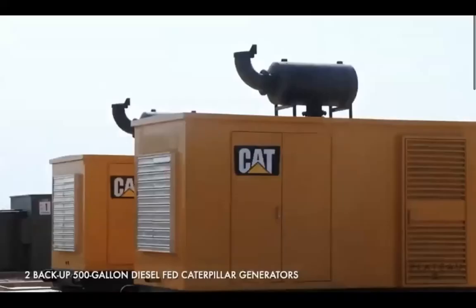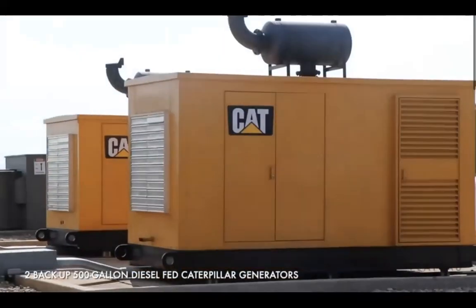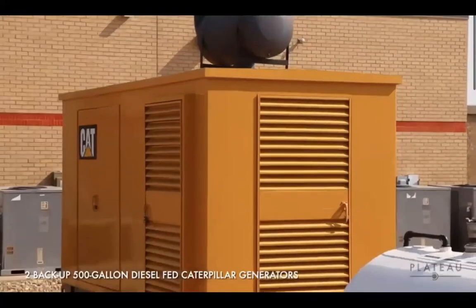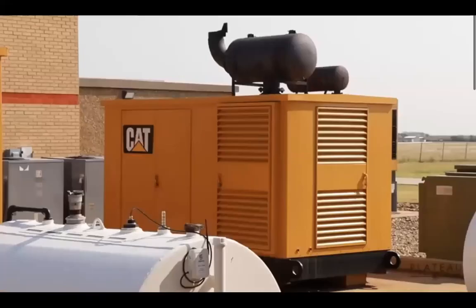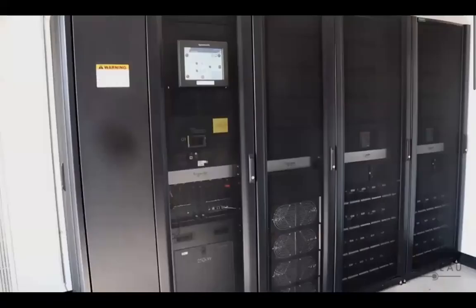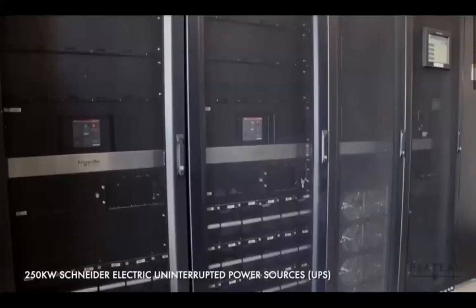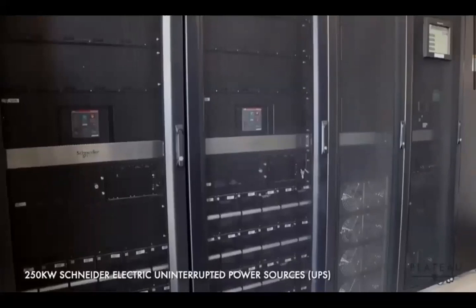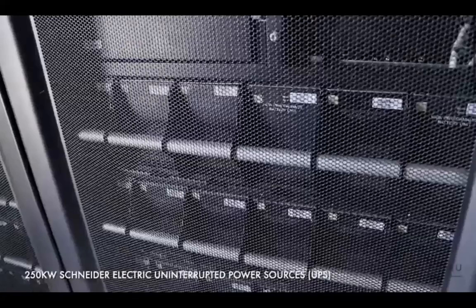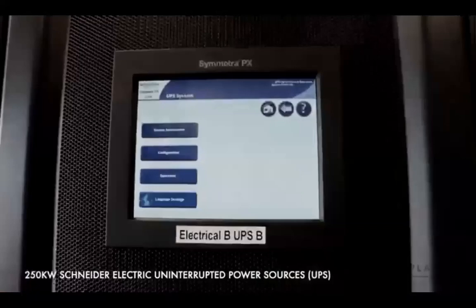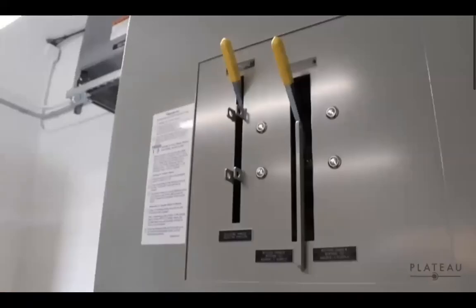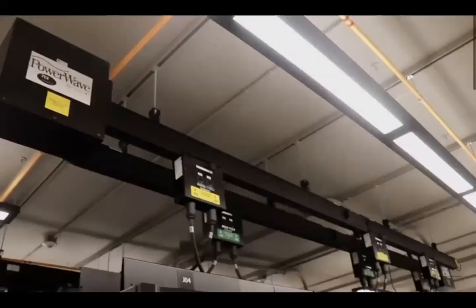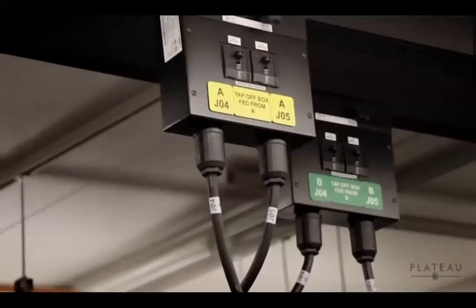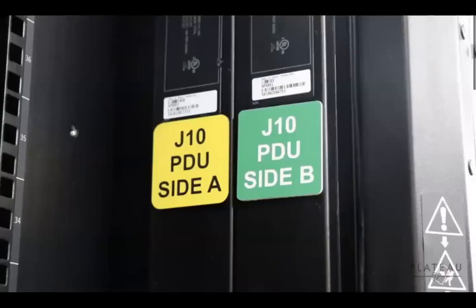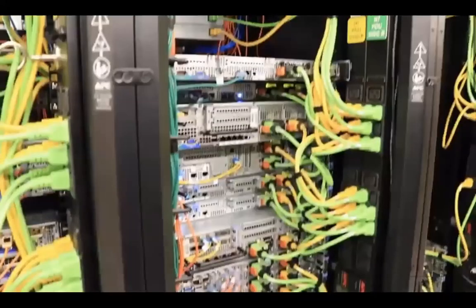Plateau ensures that the data center never sees a loss of power by having not one, but two Caterpillar generators that are each capable of powering the full load of the data center. Additionally, our data center has two fully redundant electrical rooms, each equipped with a 250 kilowatt Schneider Electric UPS. These constantly monitor the electricity sources and automatically feed the data center with power while the generator is starting up during a commercial power disturbance. Inside the pod, each server is connected to this redundant power supply, color-coded with yellow for A and green for B. A backup for our backup's backup. Now that's reliability.